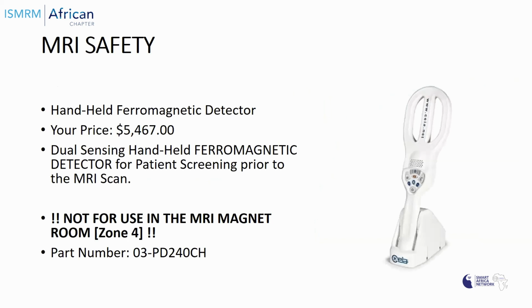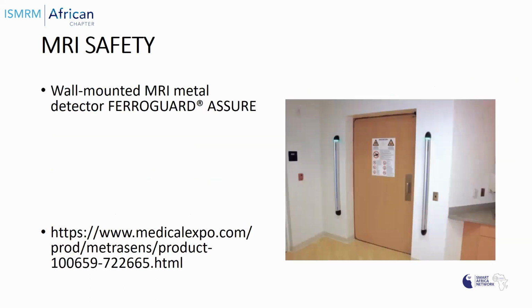And then this is also available. I saw it on the internet, but this cannot be used inside the magnet or the MRI room. We also have wall-mounted MR metal detectors. I saw this also on the internet. These are mounted at the entrance of the MR machine room so that people can scan. If there's a mistake, this can beep and alert you that you have ferromagnetic metal with you.